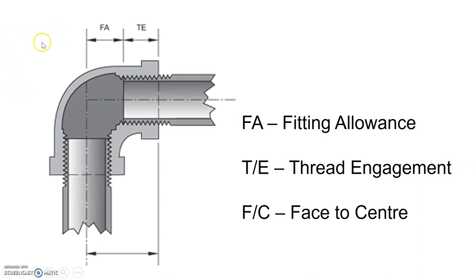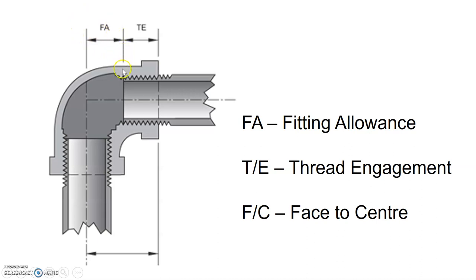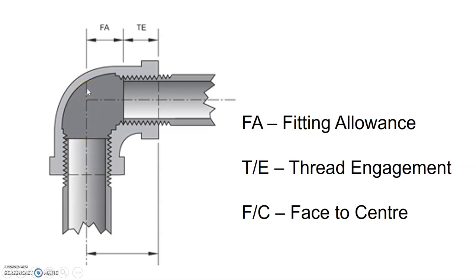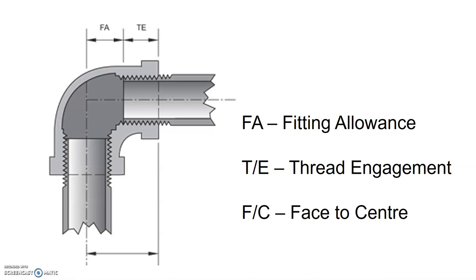When we're trying to find our fitting allowance for a black malleable iron fitting, we have to know a couple of things. First of all, we have to understand what the FA is. The FA on the diagram here shows you it starts at where the pipe stops or ends when it gets into the fitting, and it's that empty space from there all the way over to the centerline of the other outlet of the 90-degree fitting. That is known as your fitting allowance. We'll need to know this in order to find our end-to-end pipe, otherwise known as our actual cut piece pipe, because most of our measurements go from center of fitting to center of other fitting.